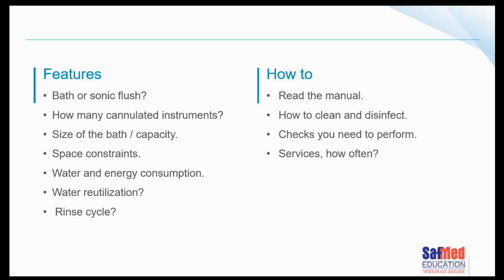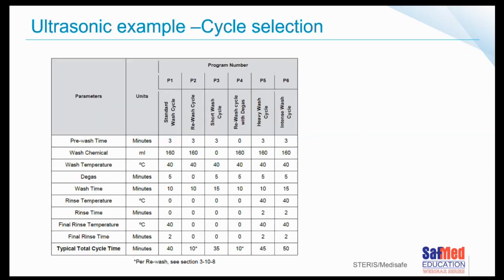You saw the complex electronics and devices and bits and pieces in that original image right in the beginning, and all of those things need to be serviced. There are pumps in there that help make that water flow for the sonic irrigation, requiring servicing. Here's an example of some types of cycles on one particular device. You can see here Program 1, Program 2, Program 3, Program 4, Program 5, Program 6, all with slightly different parameters to them. A pre-wash, a main wash, a degas. You'll note that the majority of them have a degas, except for that rewash cycle, Program 2.